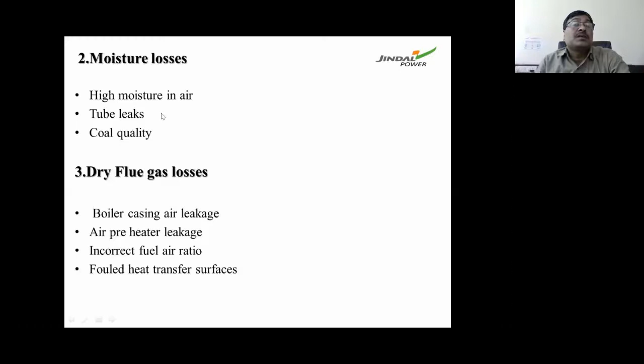Similarly, moisture in coal and moisture in air are causes of losses. Tube leaks, coal quality. Incomplete combustion is an important factor for low efficiency, which is due to coal quality, increases in ash content, carbon content, decreased coal mill fineness, classifier vanes not properly adjusted, mill ring roll wear, mill classifier vane wear, and sometimes burner tips plugged or eroded. These need regular maintenance.